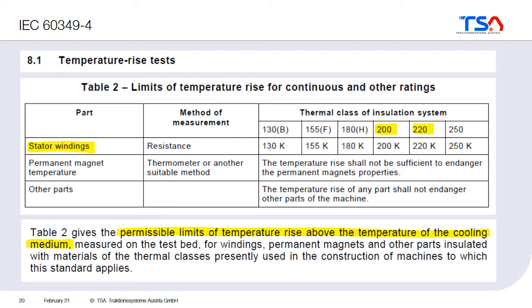There are also other parts in the machine where temperature can be critical — for example the permanent magnets and the bearings. Because there are so many different materials and it depends on the design of the machine, you cannot specify a single value for temperature rise for these parts. The standard only tells us that the temperature rise shall not be sufficient to endanger the permanent magnets or other parts of the machine.